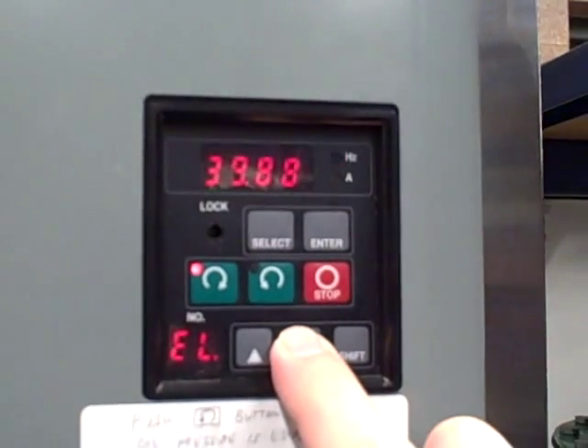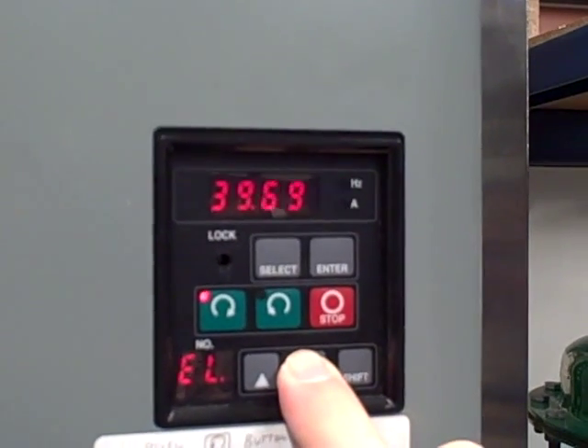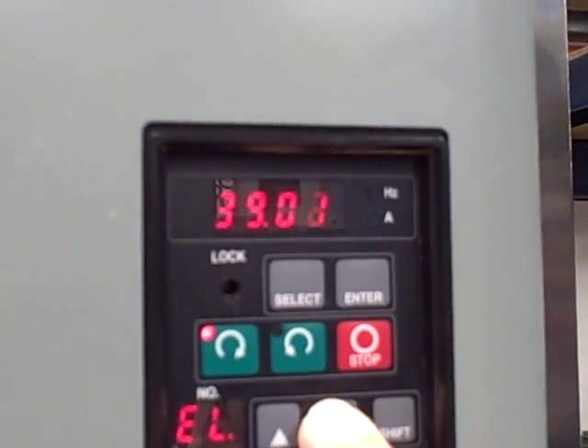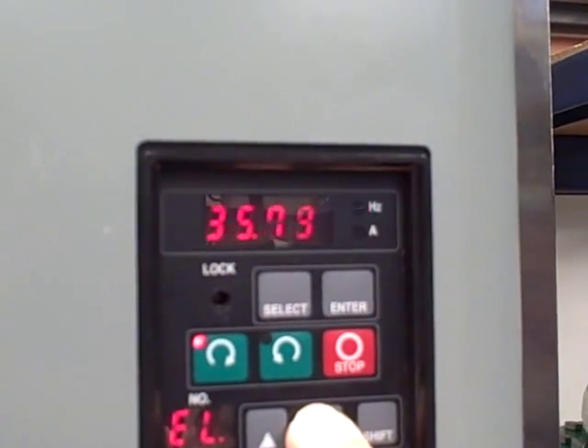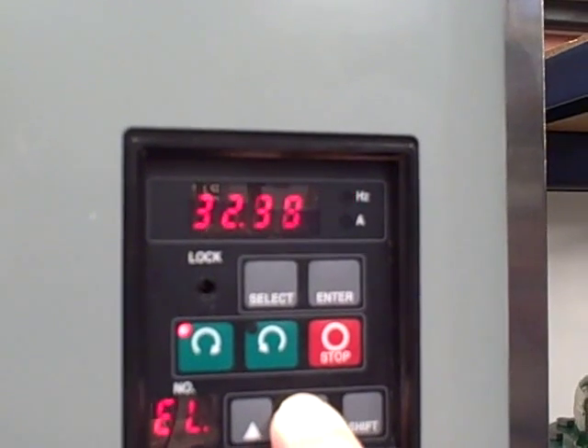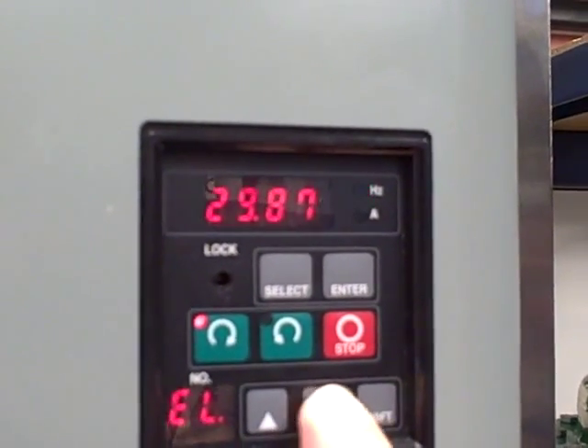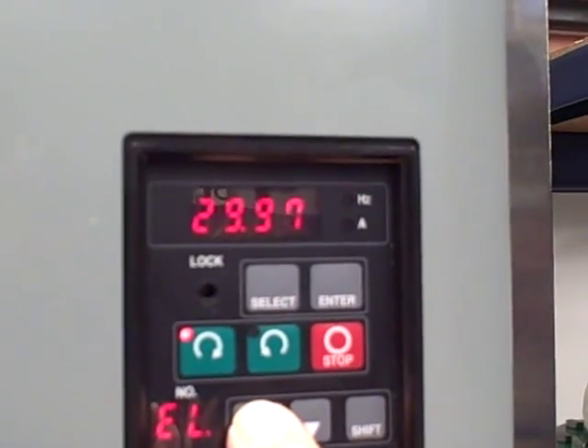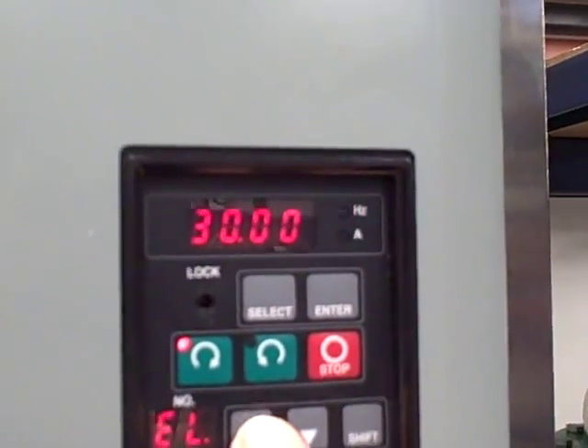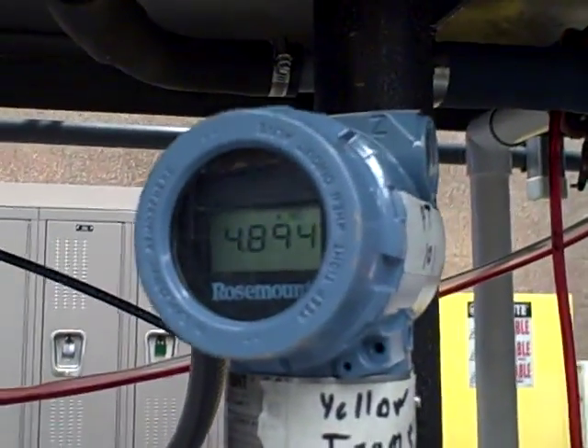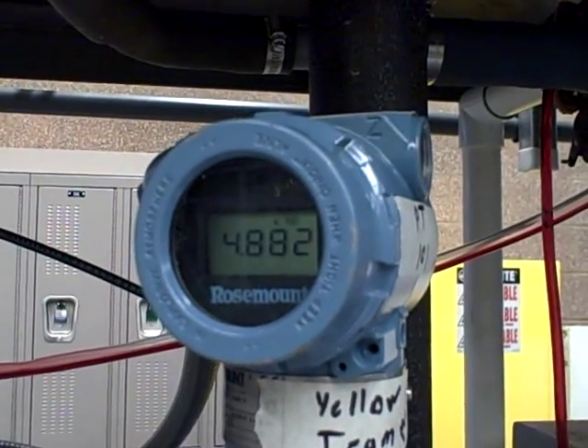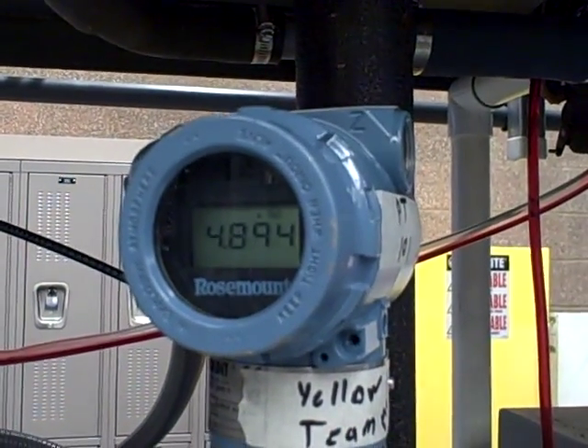So here we go once again. You can hear the motor slowing down. 30 hertz. We come over here and it reads 4.882, 4.89 inches of water.